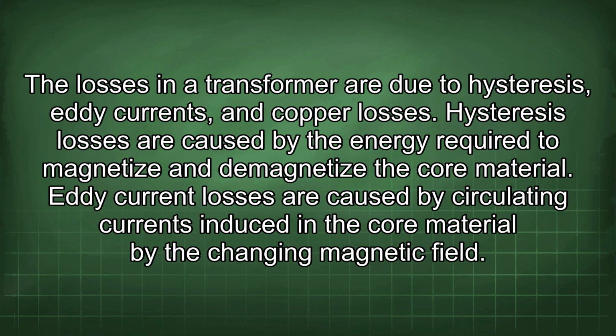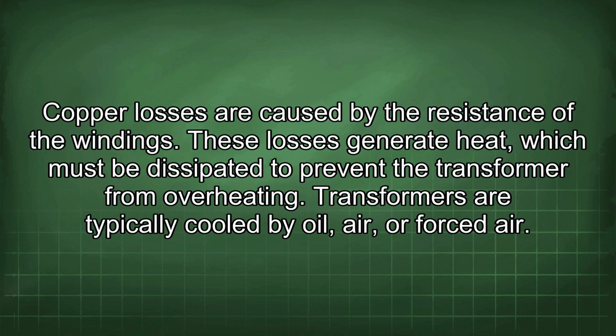The losses in a transformer are due to hysteresis, eddy currents, and copper losses. Hysteresis losses are caused by the energy required to magnetize and demagnetize the core material. Eddy current losses are caused by circulating currents induced in the core material by the changing magnetic field. Copper losses are caused by the resistance of the windings. These losses generate heat, which must be dissipated to prevent the transformer from overheating.